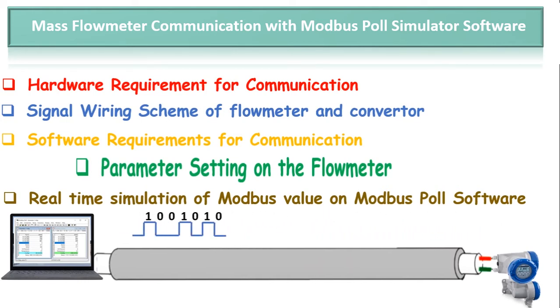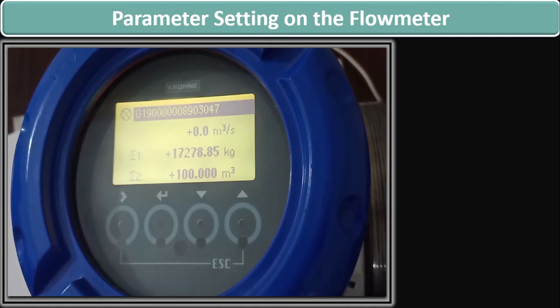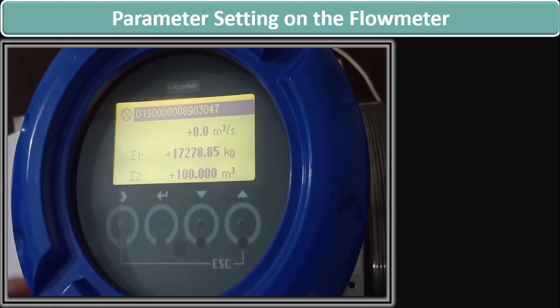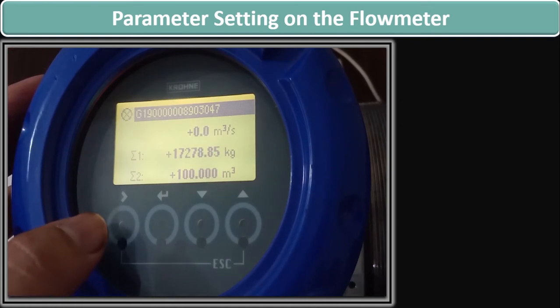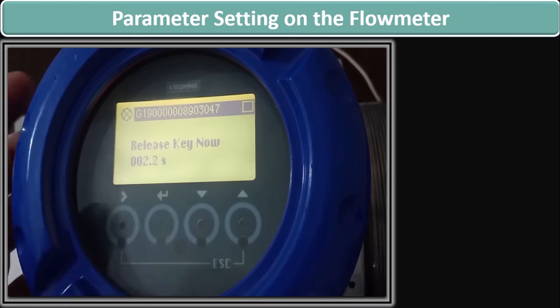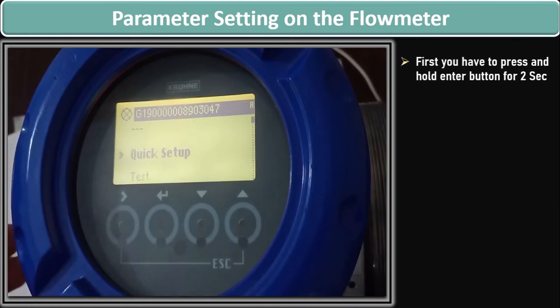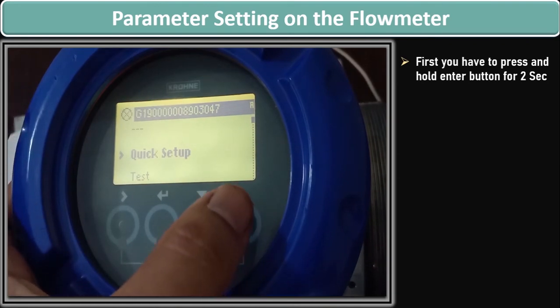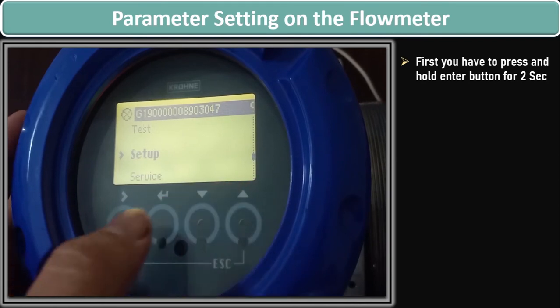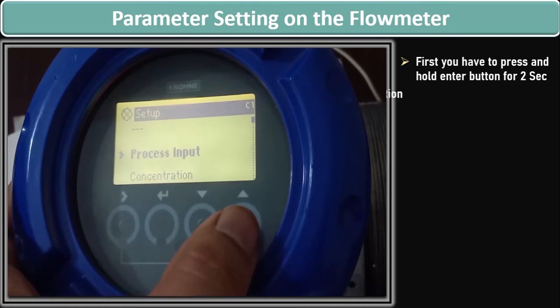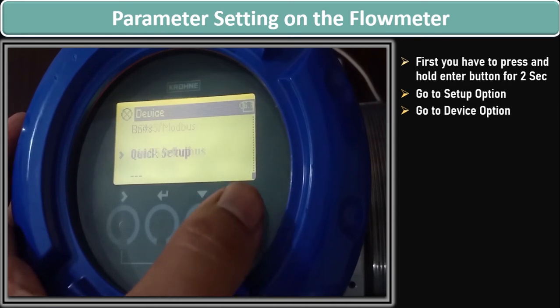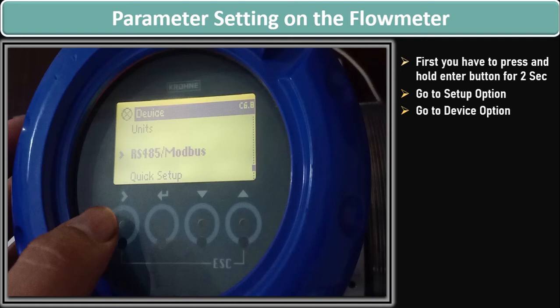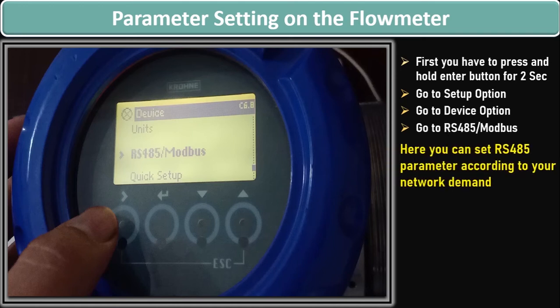So let's see the parameter setting on the flow meter. The front screen of the Krohne MFC400 converter displays the value along with four buttons through which we go into the setting and check our Modbus RS485 parameters. To enter into the flow meter setup you have to press and hold for 2 seconds. After holding this you enter into the setting options. In settings, click the upward direction to find the setup option and enter into setup. In the setup option, find the device option and enter into it. In the device option, find the RS485 Modbus option and enter into it when it is highlighted.